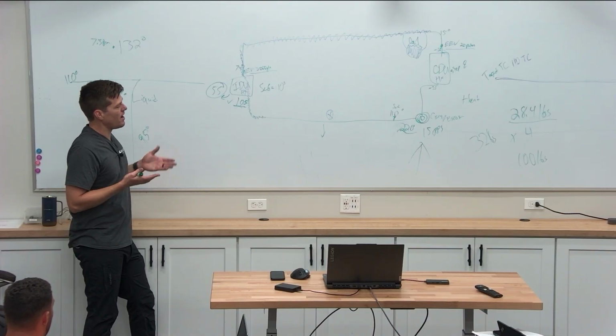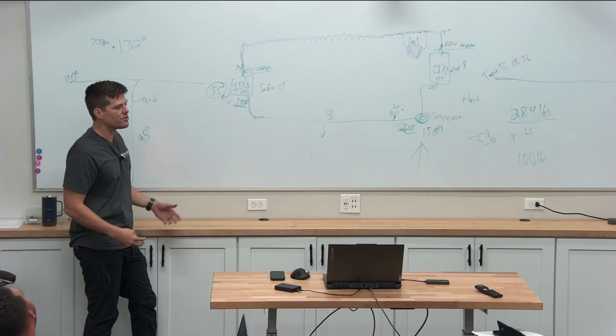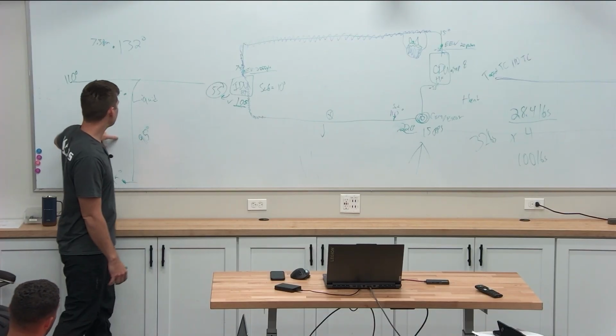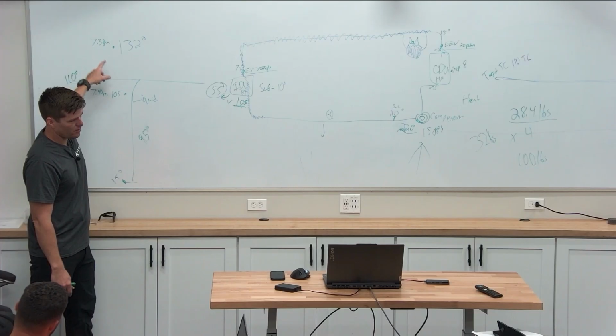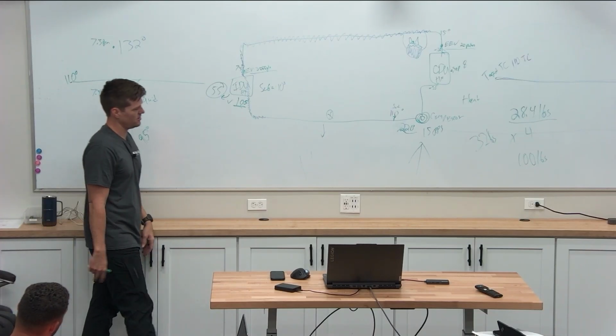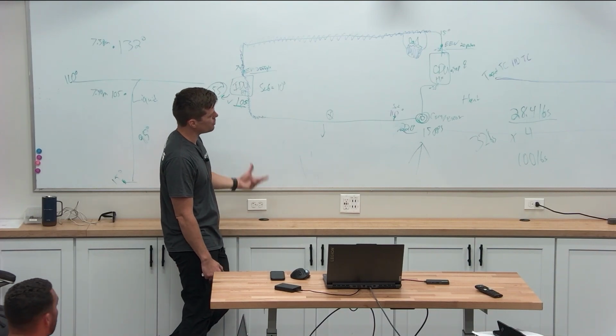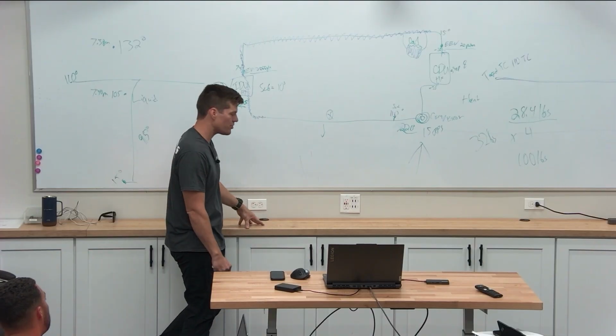This is what happens when you have 5 technicians go out and look at it, but they never step back to look at the basic refrigeration of it to determine where it falls on my saturation chart. Where does it fall within my system and what does it look like? Is it a vapor or is it a liquid? And so then we say your system's overcharged. There's no way to actually determine the total charge of it.